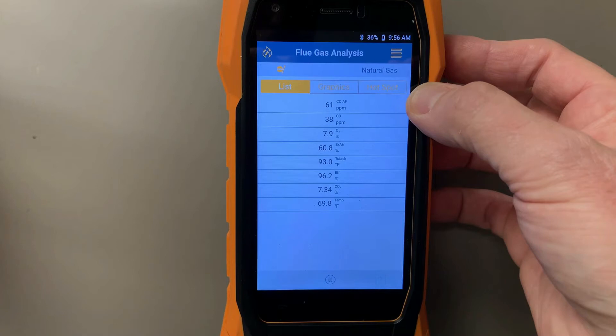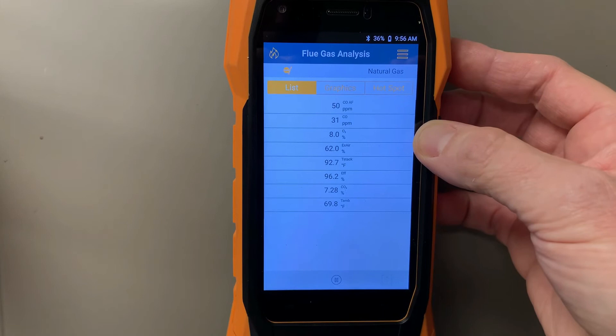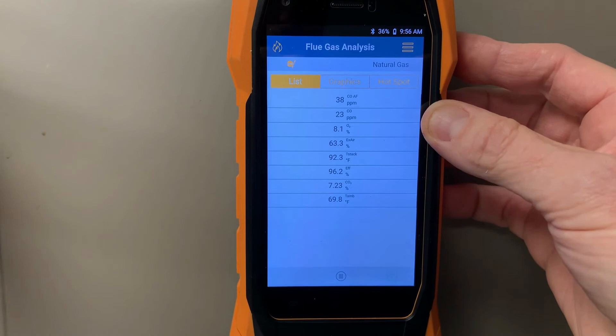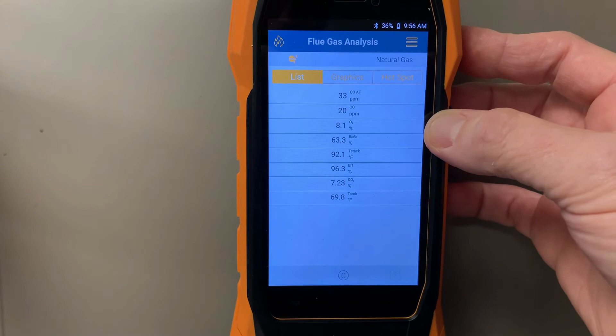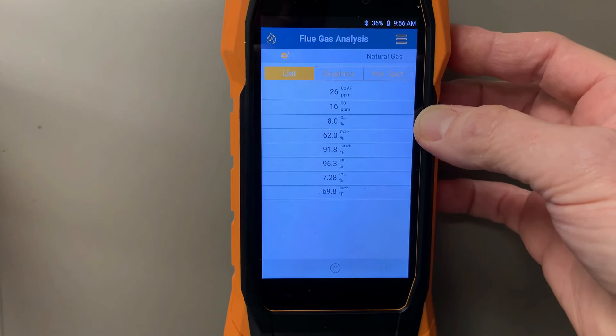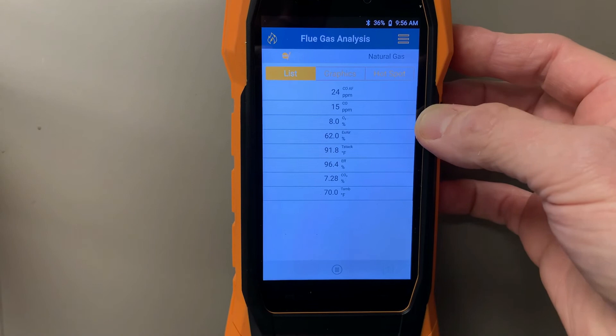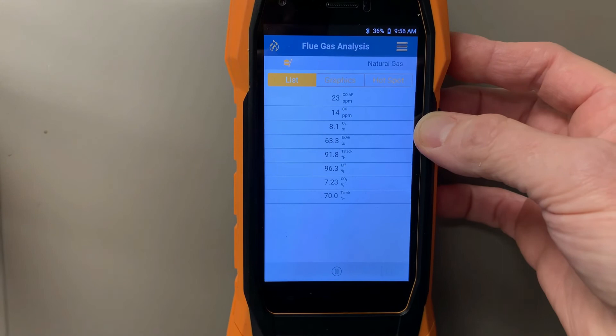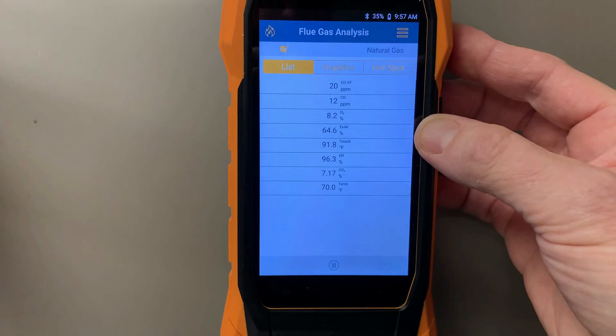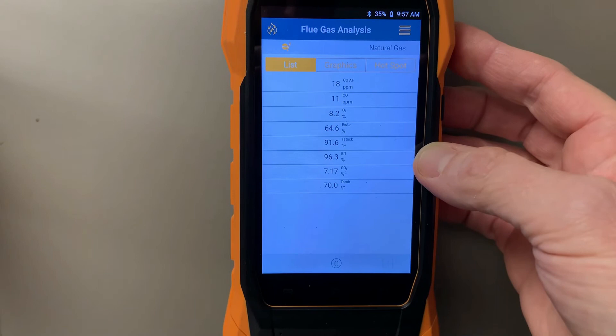We're going to let this stabilize out and keep an eye on it. Right now we're running about 60 parts per million CO air free in the flue — a good number. We're running about 8% O2 with the burners and blower on. Under 50 parts per million and 8% O2 — anywhere between 6 and 9 is a pretty good number. Also watch that O2 is not dropping; if it drops from 8 down to 7, 6, 5, 4, that indicates the secondary is probably not draining and is filling up with water. Right now we seem very stable — 8% O2, 20 parts per million CO air free. Stack temperatures look good, efficiency at 96.3%.